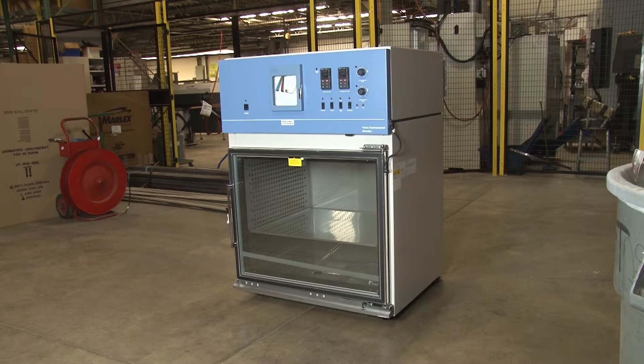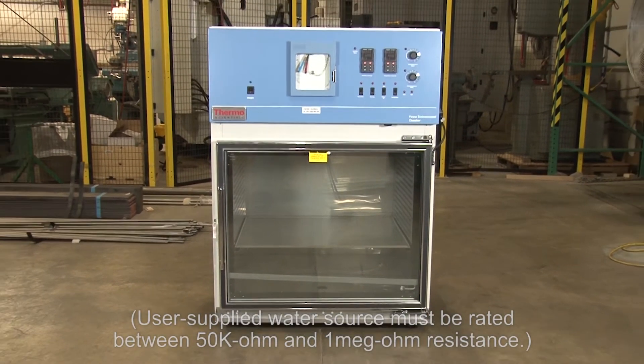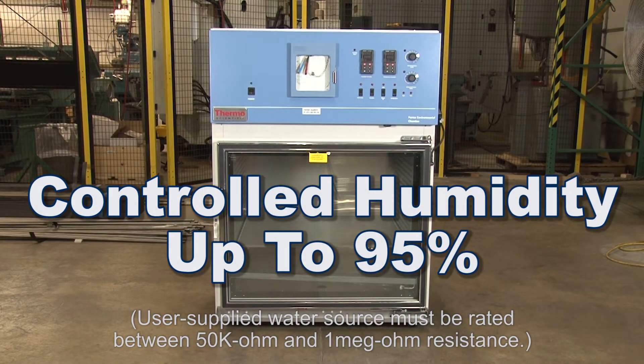Heat is provided by two 600 watt wire wound elements and cooling is supplied by a quarter horsepower non-CFC compressor. A steam generator provides controlled chamber humidity up to 95%.